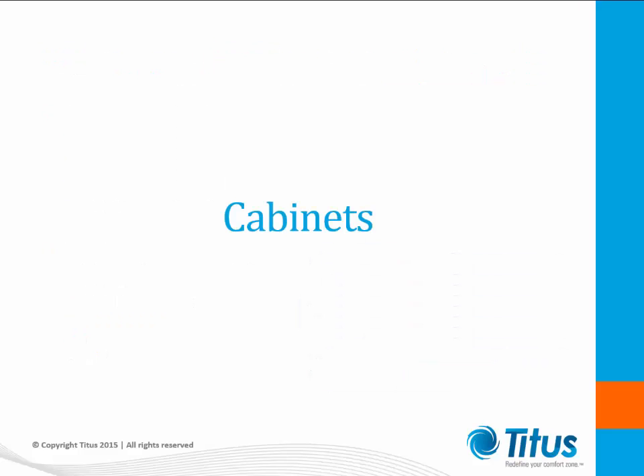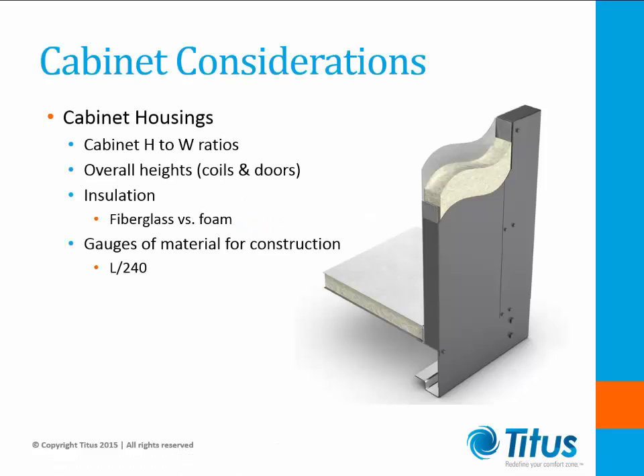Let's start with cabinets. There are several different cabinet considerations that need to be observed. Cabinet housing ratios of 0.6 to 0.9 yield shorter unit lengths. Sizing in this method provides a variety of cost-effective fan choices by allowing motors to be mounted beside the units within the housing. Overall unit heights may have their place, but in many of those cases, stacked coils and tall doors are typically cost drivers when building a cabinet.